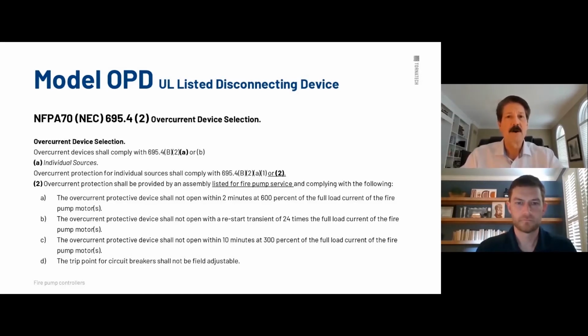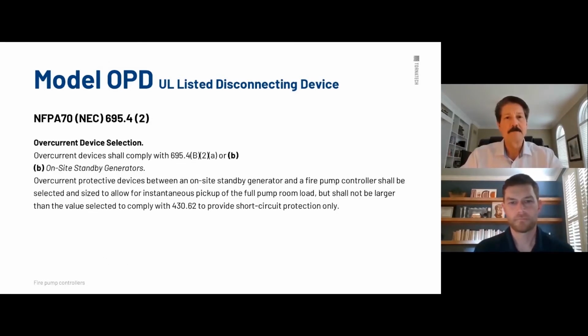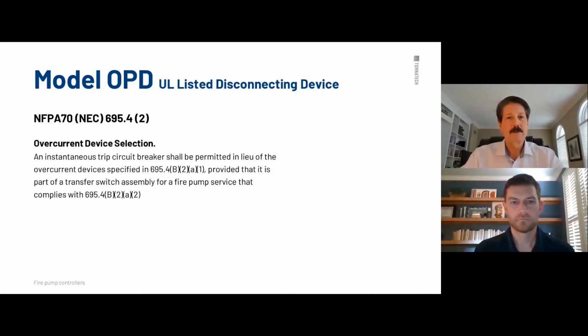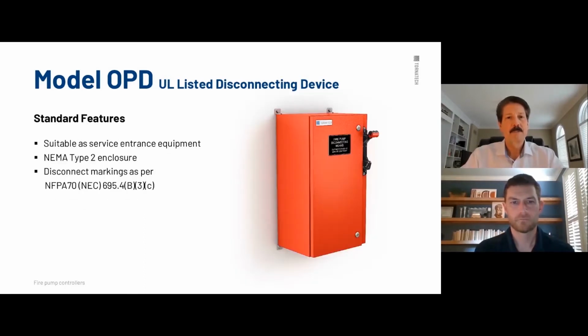But the OPD itself is a UL-listed disconnecting device, the only one at this time that is to be used only with a UL-FM fire pump controller. That's the whole purpose of the OPD. That's why we designed it. I'm going to click through here a little bit. Let's get right into it here.